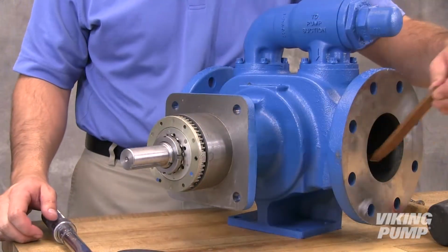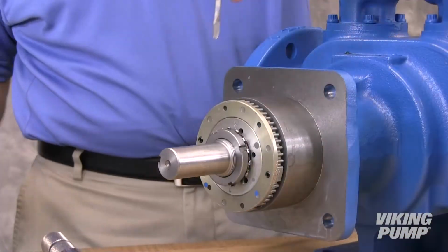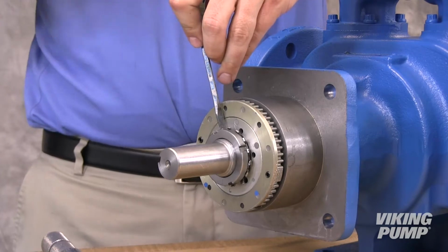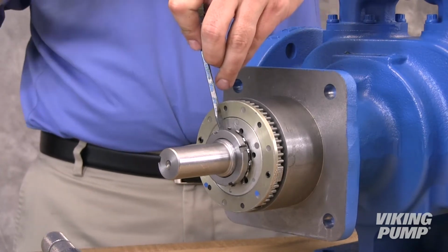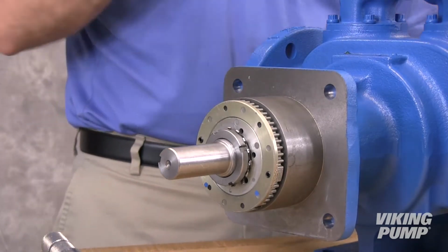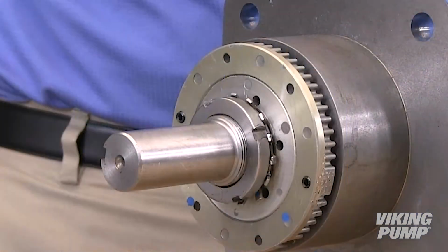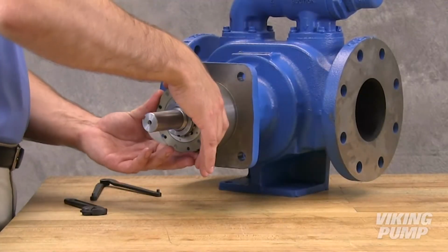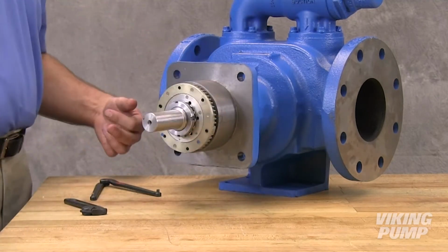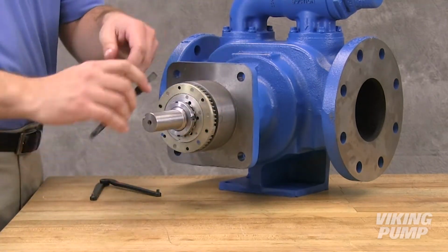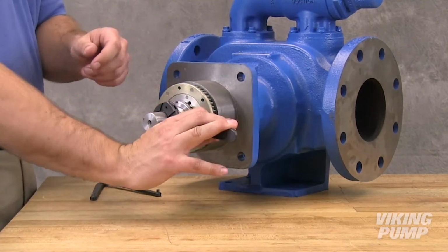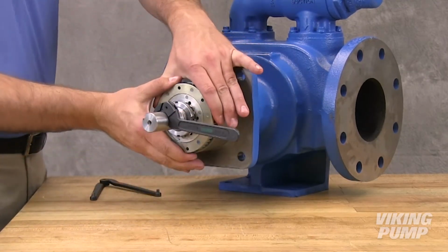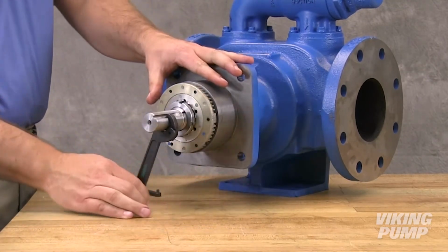Remove the brass bar. Bend a tang of the lock washer into a slot of the lock nut. If a tang does not line up with the slot, tighten the lock nut until it does. Failure to tighten the lock nut or engage the lock washer tang could result in early bearing failure and cause damage to the pump. Tighten the thrust bearing assembly clockwise until the shaft can no longer be turned by hand. Then loosen until the rotor shaft can be turned with a slight noticeable drag. This point is known as zero end clearance.